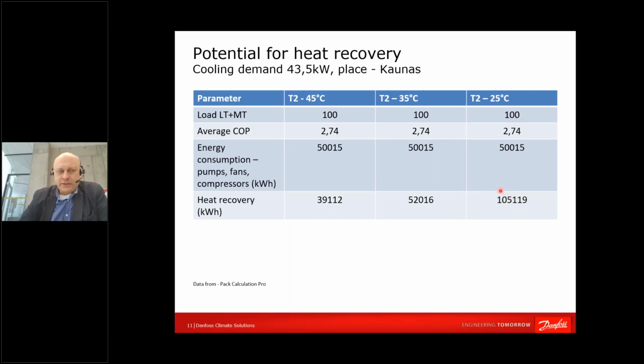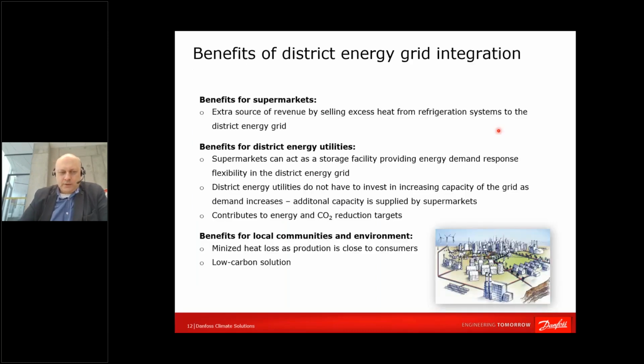So again, when speaking, HVAC and cooling guys, talk to customers, talk to supermarket chains. Don't be afraid of a twice larger coil in your air handling unit. Yes, you will increase space in the air handling unit. On the other hand, with a delta T of 30 degrees for the cooling, your pipes and all the rest, like valves, fittings, whatever, and labor cost will decrease because the flow will be lower. Another benefit, of course, might be, as I spoke, that energy could be sold back to district energy. So maybe some companies would be interested in buying energy from supermarkets.